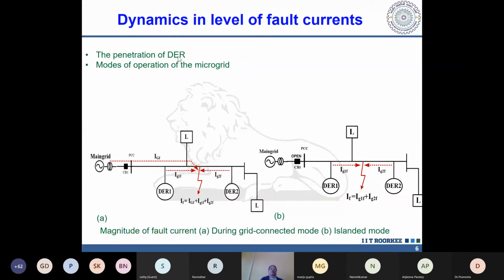The second reason is the penetration of DER. If you penetrate renewable sources into the existing grid or AC microgrid, low voltage smart grid, you are indirectly modulating the current magnitude. Even forgetting the fault case, suppose there is no fault - the pre-fault current through this line still varies with the absence or presence of DER.